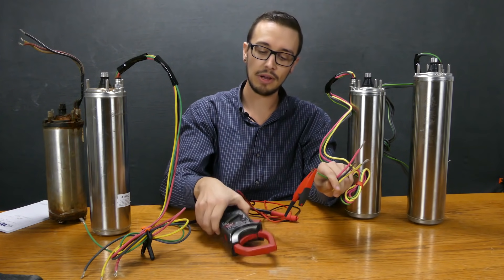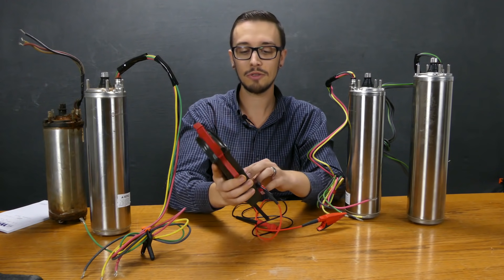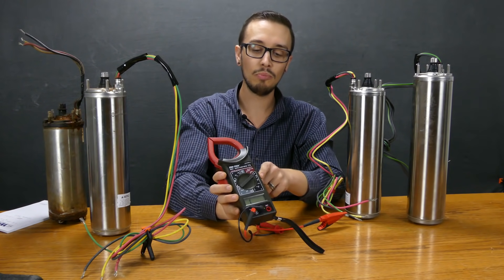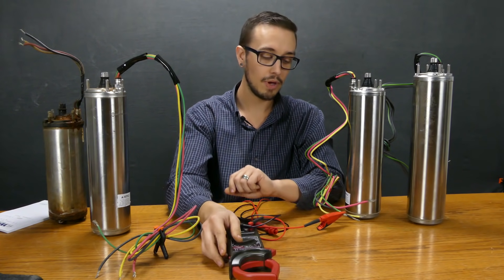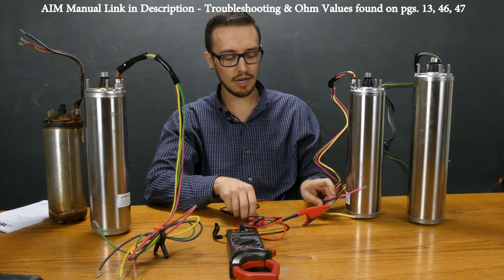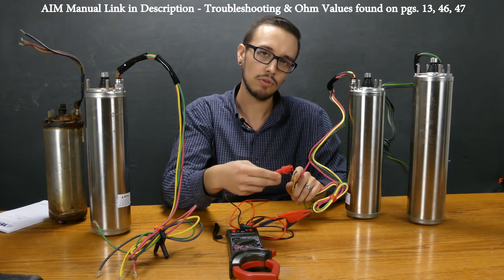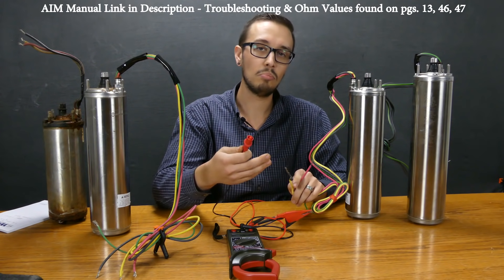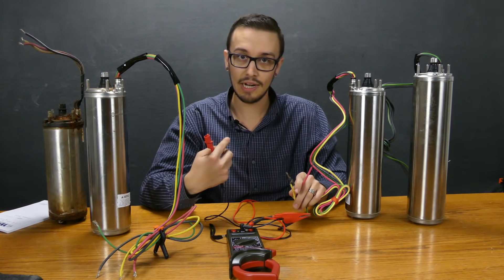For this test, this meter actually isn't ideal. I have the ohm meter set to the highest setting - the two million ohms. What we're looking for - and there's a chart in that AIM manual that's going to actually tell you - but basically a number below 500,000 ohms, that's the threshold for pull it out and replace it.